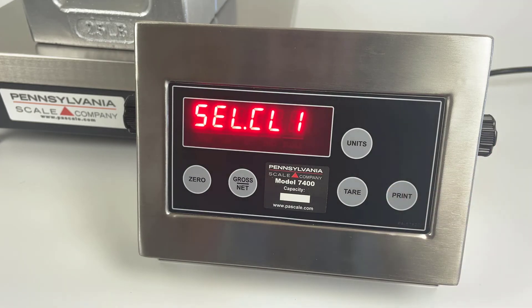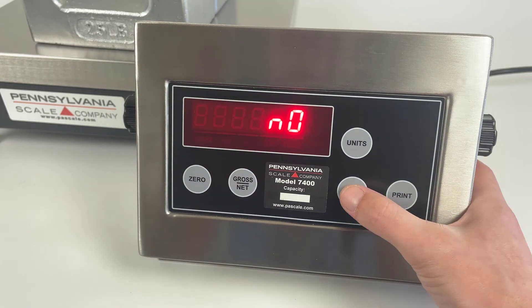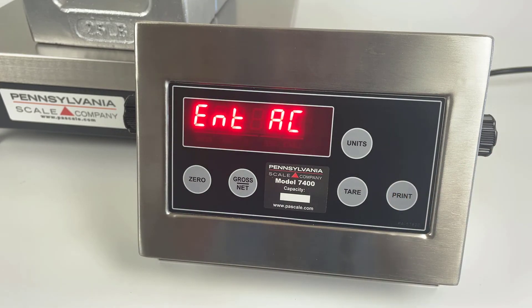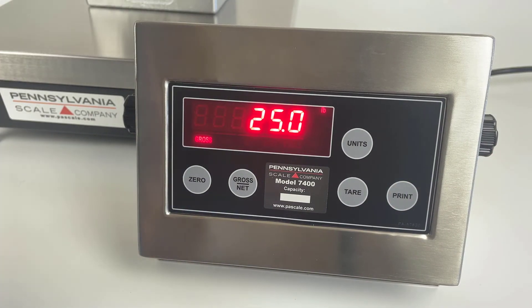When you are finished, press the print key to return to the main menu, then press print again to see the save screen. The tare key changes 'no' to 'yes', and then print confirms. The ENT AC screen allows you to change the access code, or you can press the print key to return to weighing mode.